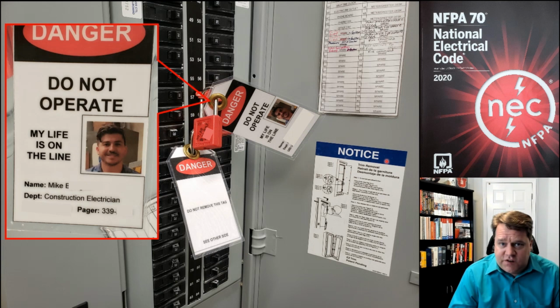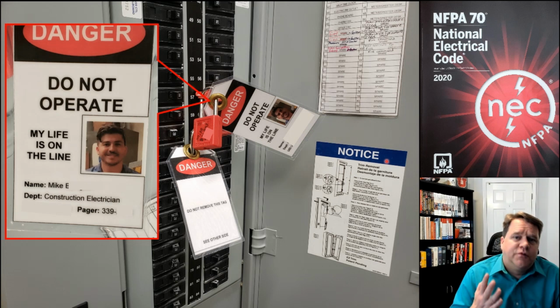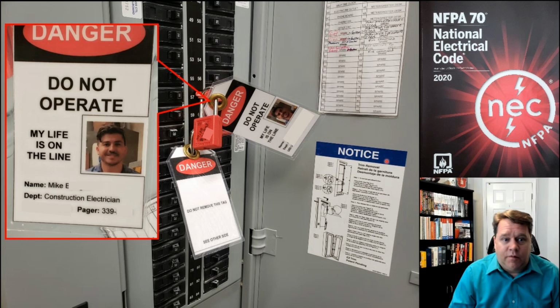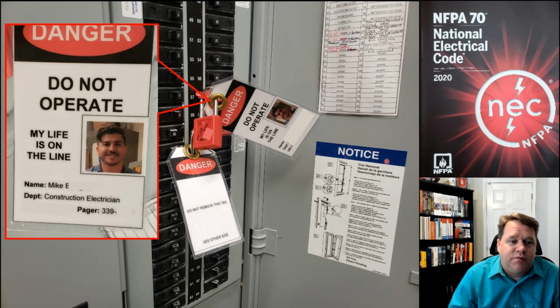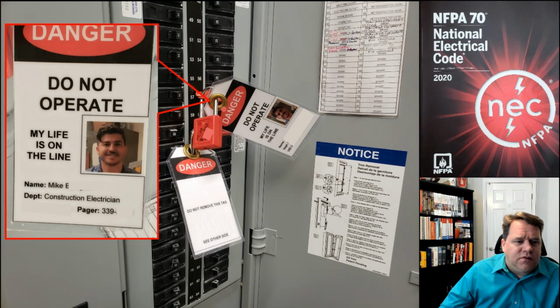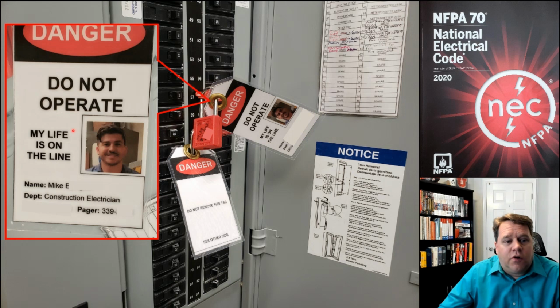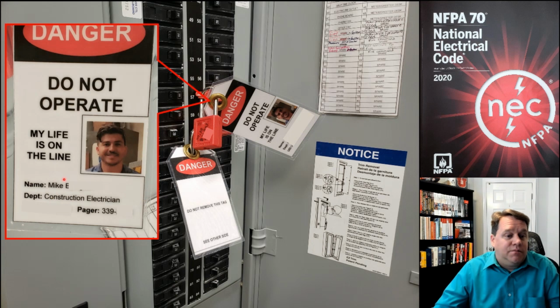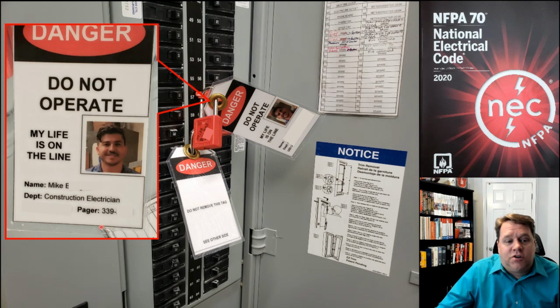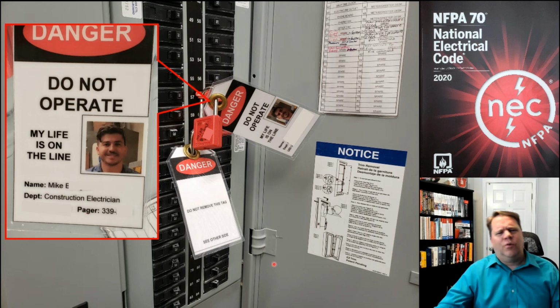If you're at a large facility, I highly recommend personalized tags like this one. I think this is an absolutely great example of a tag. So this is at a hospital that I was touring. And when I was there, they happened to have a breaker that was locked out at the time, and I was able to snap some pictures. And it says, danger, do not operate. Well, obviously, and it says, why should I not operate it? Well, because my life is on the line, and I'm a real person, and I have a real face, and my name is Mike. My department, construction electrician. Here's my number if you need to get in touch with me. Of course, this has a pager, and it's like, what year was this?